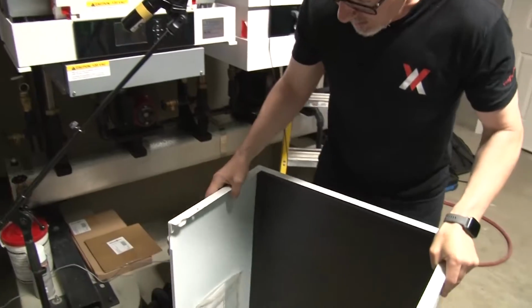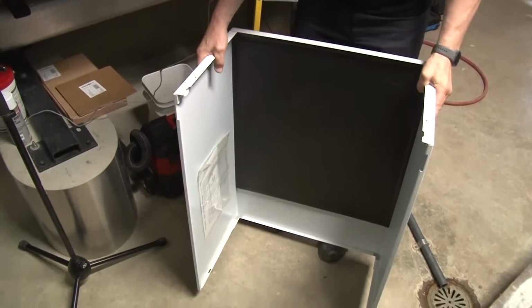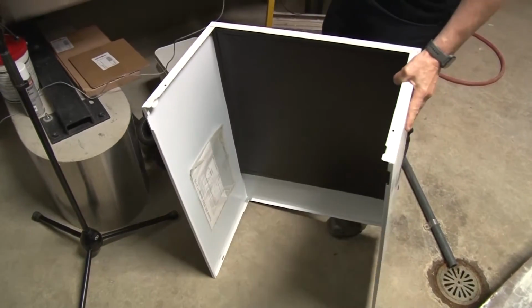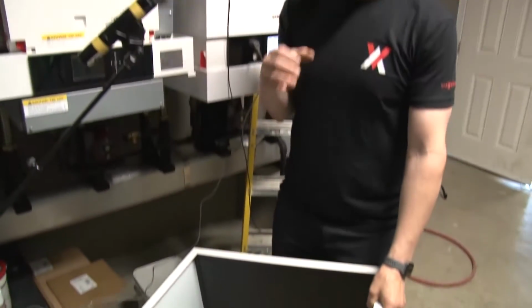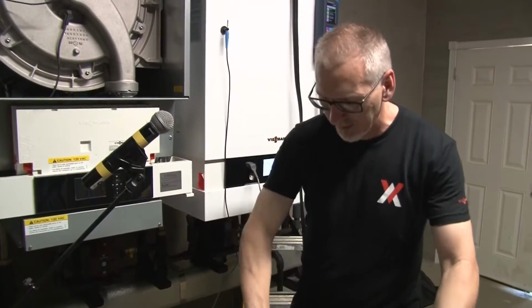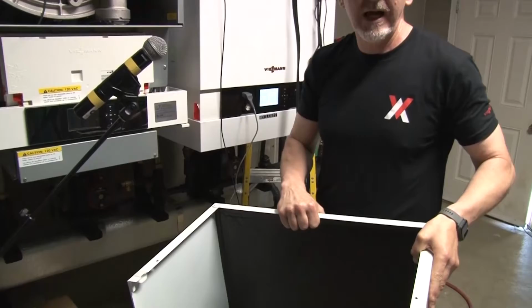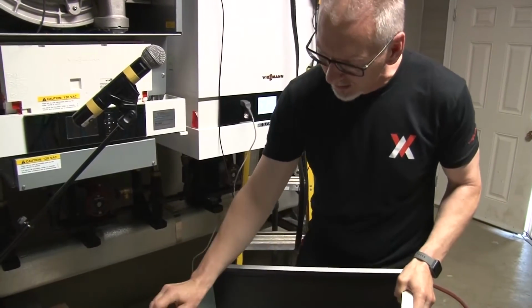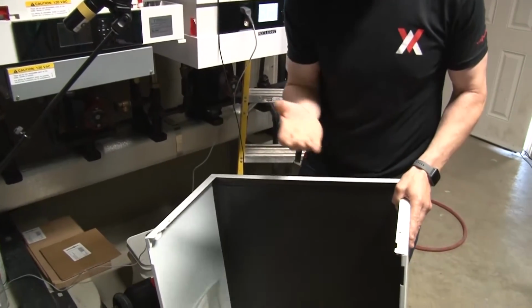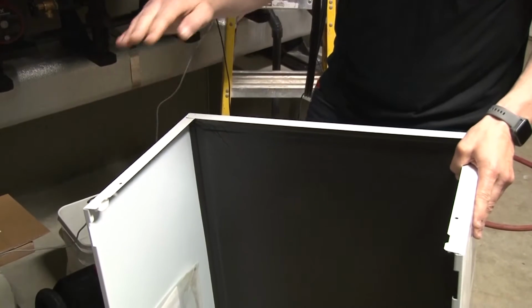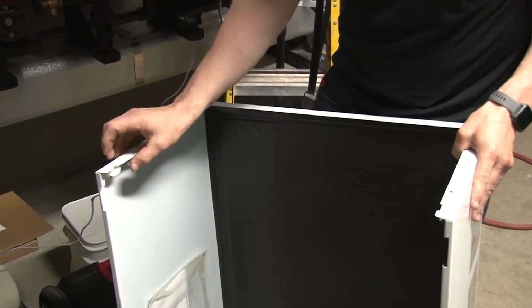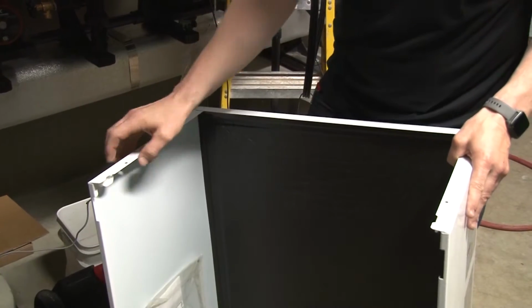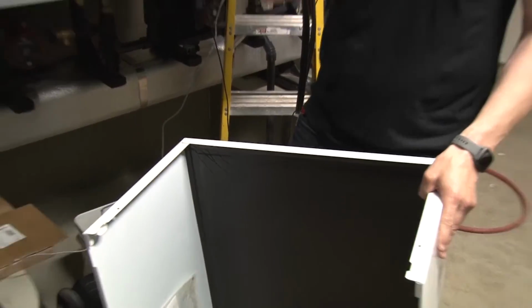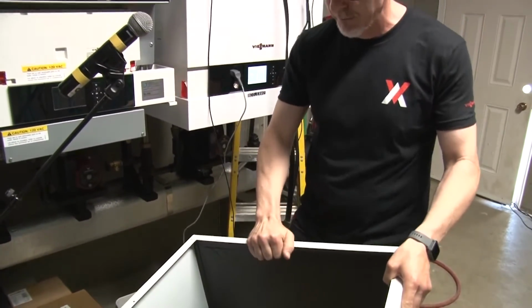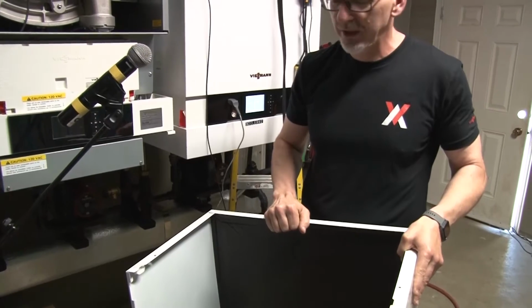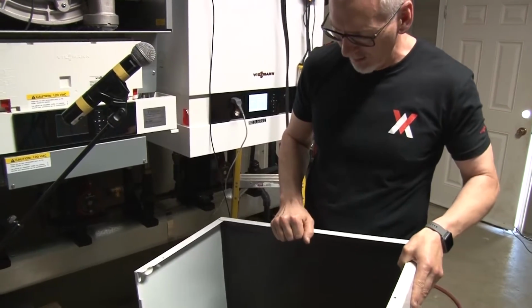Important to note that when we take these doors off, we lift them up. So we're going to lift the cabinet up and then pull it towards us, versus just grabbing the top of the boiler and heaving that thing towards you. The reason I say that is you've got these little plastic clips and they slide the door into place, and I've seen these little hinges break, these little clips will break as a result of just reefing on the top of the boiler. So lift it up and pull that door towards you is what we would recommend.